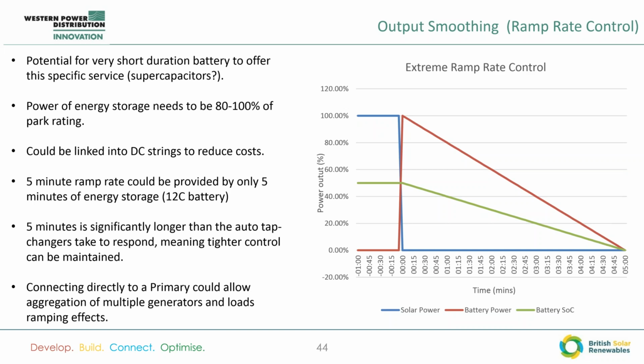5 minutes is significantly longer than tap-changers take to respond, so much tighter control of the voltage on these networks could be maintained. And that graph on the right there is demonstrating how even a 100% solar power drop, you can reduce it to a gradual decline over 5 minutes, just with 5 minutes of energy storage at 50% there.